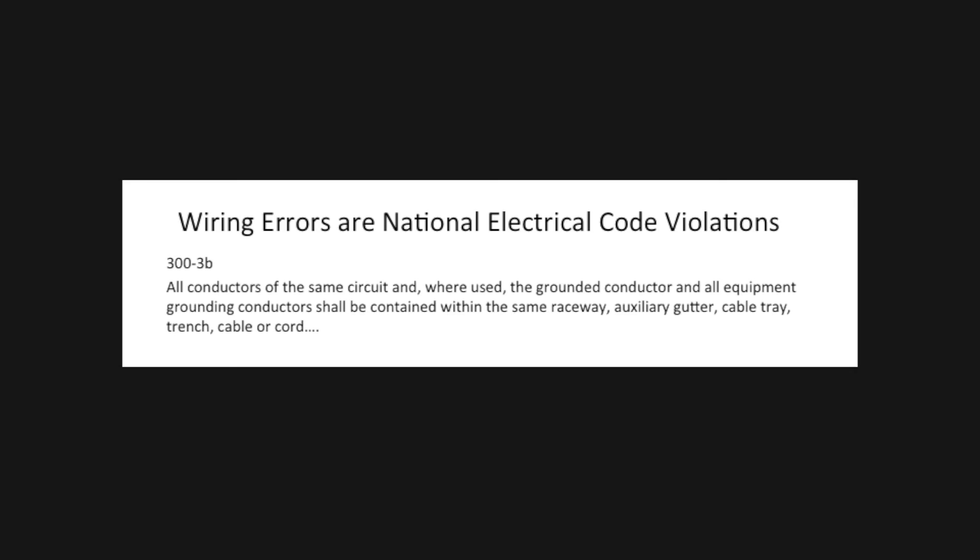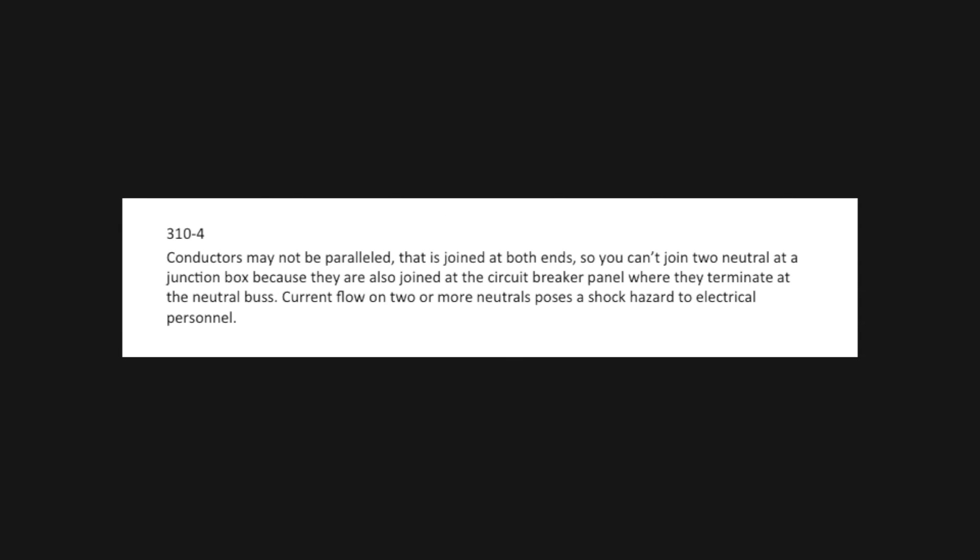The code citation is 300-3b, which states all conductors of the same circuit, and where used, the grounded conductor and all equipment grounding conductors, shall be contained within the same raceway, auxiliary gutter, cable tray, trench, cable, or cord. NEC 310-4 states conductors may not be paralleled — that is, joined at both ends — so you can't join two neutrals at a junction box because they are also joined at the circuit breaker panel at the neutral bus. Current flow on two or more neutrals poses a shock hazard, and the magnetic field generated will cause disruption of sensitive electronic equipment like computer servers.